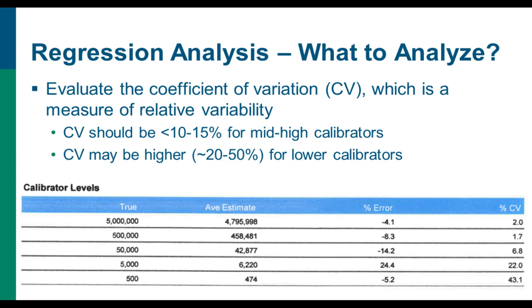In addition, you'll want to look at the coefficient of variation, which is a measure of relative variability. We use this for quantitative molecular assays. This is one from one of our assays, I believe EBV, and this is analysis from the instrument. If you look at the coefficient of variation in the far right column, for your mid to high calibrators, your CV should be low, less than 10 to 15% ideally. At your lower calibrators, you're going to have more variance, so your CV is automatically going to be higher. It's recommended to keep that within 20 to 50% or so. If you see that start to creep up to 60 to 70% or higher, you're going to run into some issues. That's really just to make sure that there's not a lot of variation in your curve and within your assay.